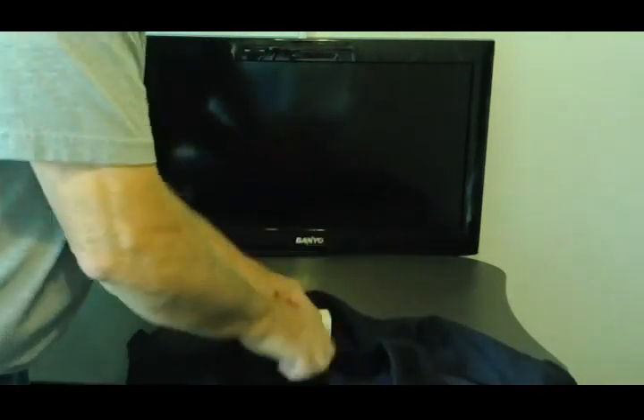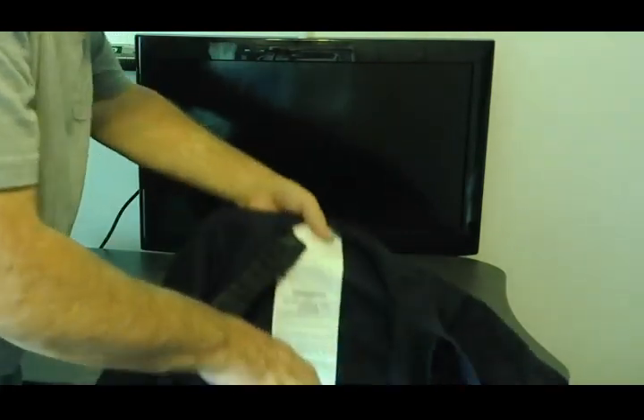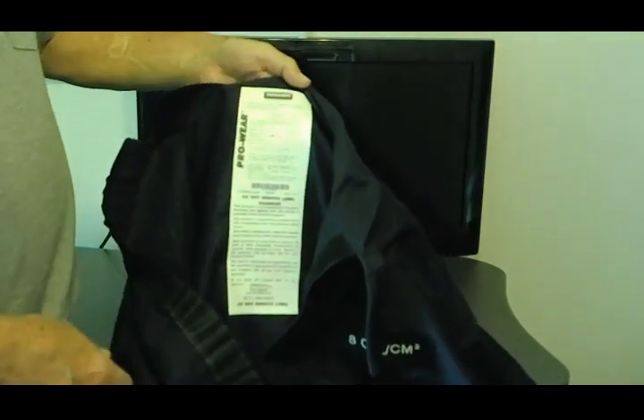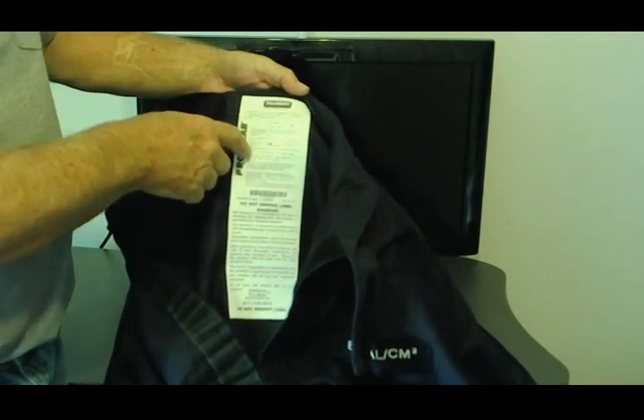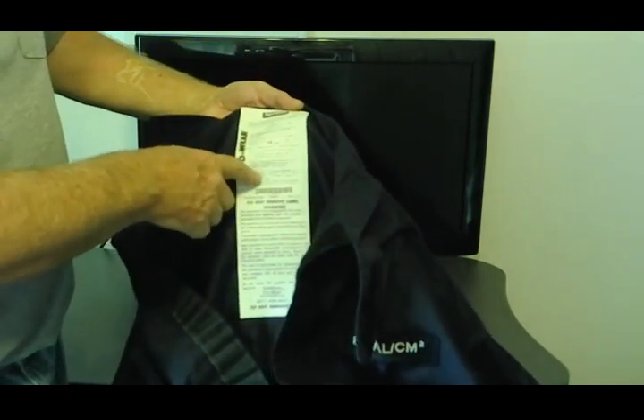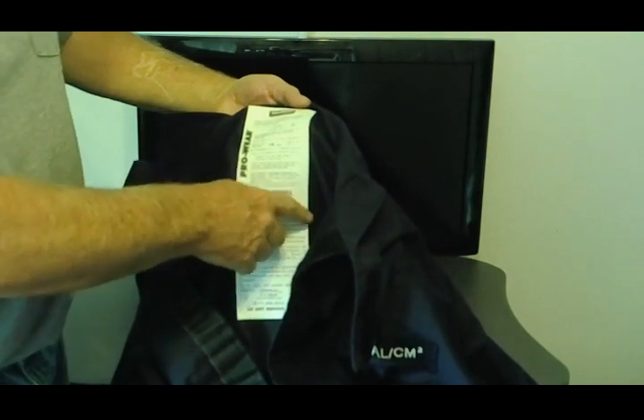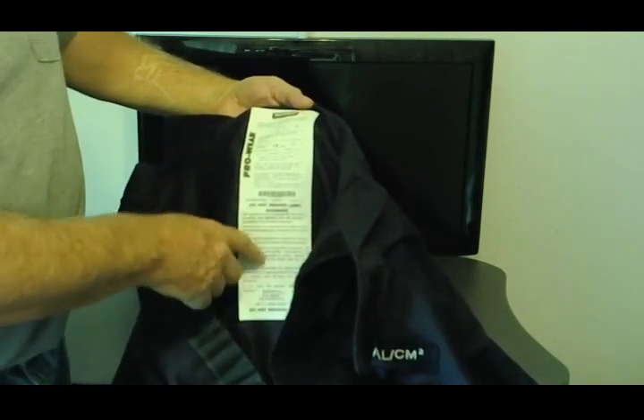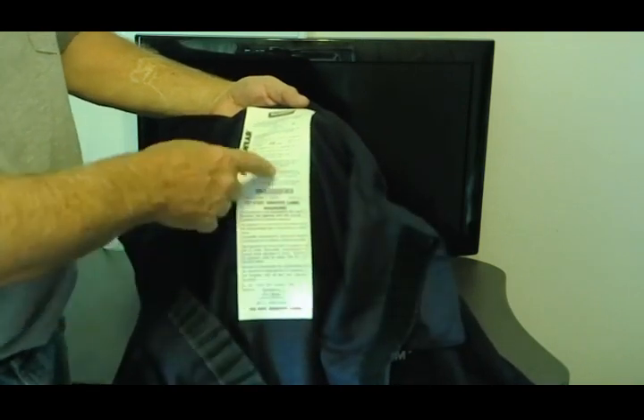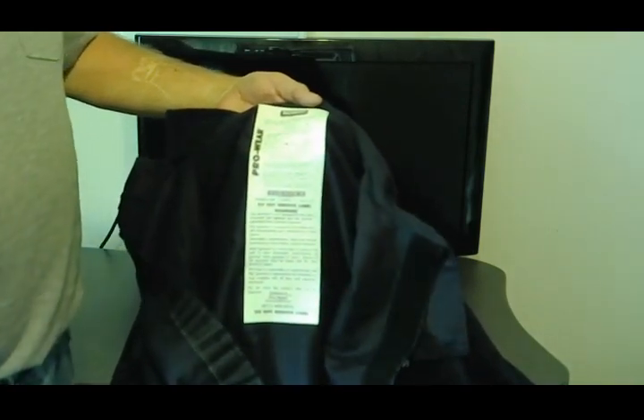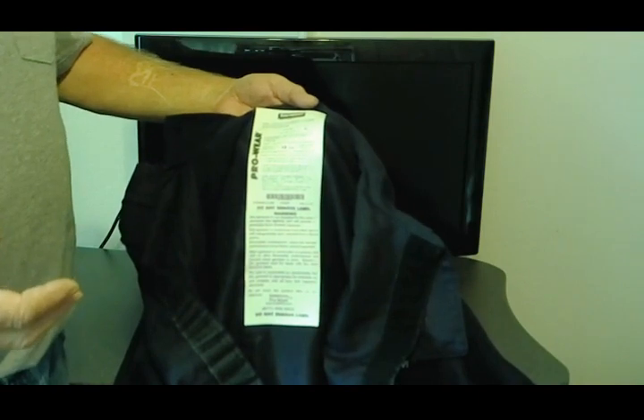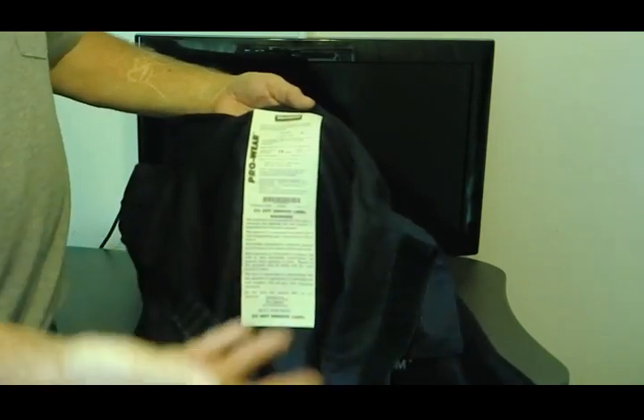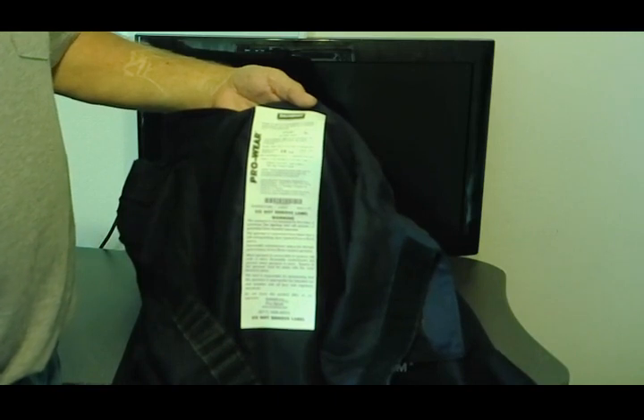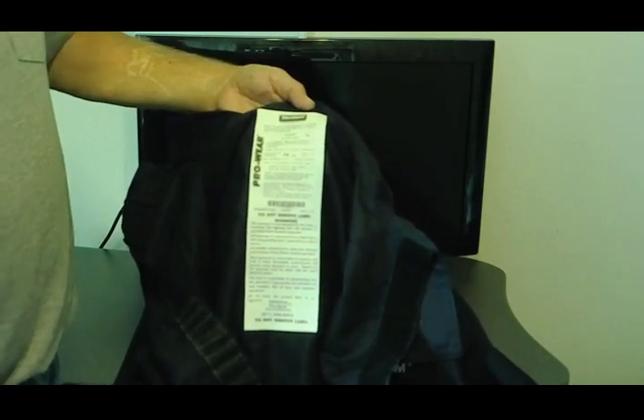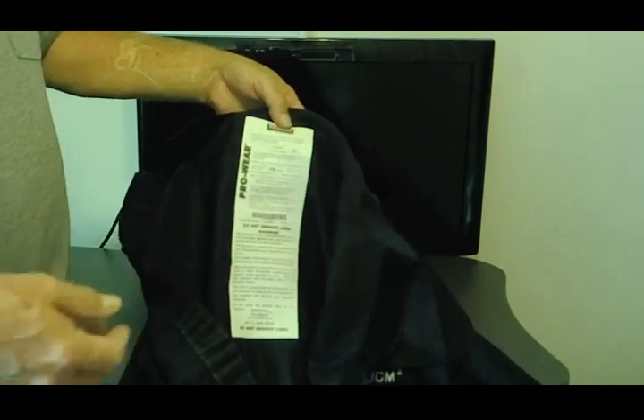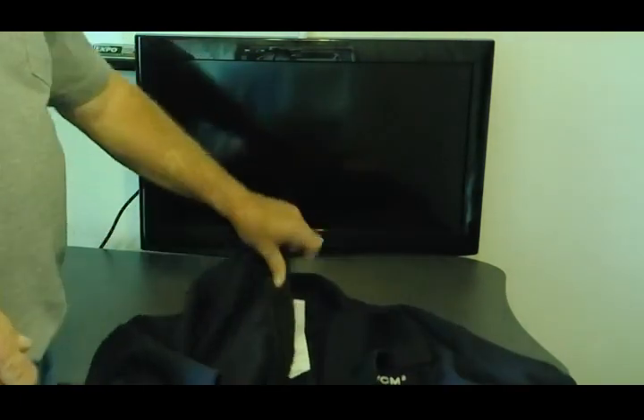Now, if you're not sure about how things work with the PPE, just like this one, it has a very good label on the inside. This label gives me the size, the arc flash ratings, the standards it's made to, and it also tells you how to clean and take care of the garment. Because these kinds of garments have to have specialized care, specialized soap, specialized laundering. If you don't follow the labels to the letter, it's no longer arc rated. All the arc rated properties and chemicals are washed out. So these should be inspected every single time they're used.